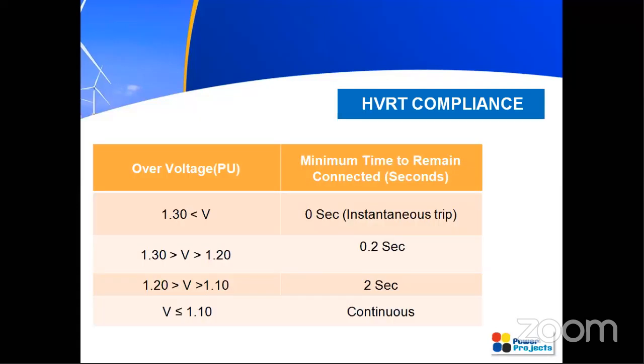So coming to the HVRT compliance, we have seen LVRT, low voltage ride through, that is voltage dip. Similarly, for high voltage ride through, HVRT, whenever your grid faces high voltage, the point of interconnection between your wind turbine and the grid should remain connected. That is the point they are stressing in HVRT compliance. This is clearly depicted in the table, and I will explain this table. Whenever the voltage is less than or equal to 1.1 per unit, that is, it increases from 1 per unit to 1.1 per unit, your wind farm has to remain connected continuously to the grid.